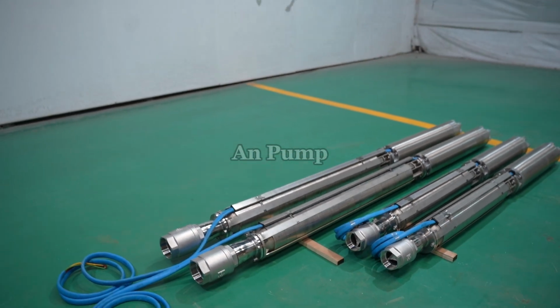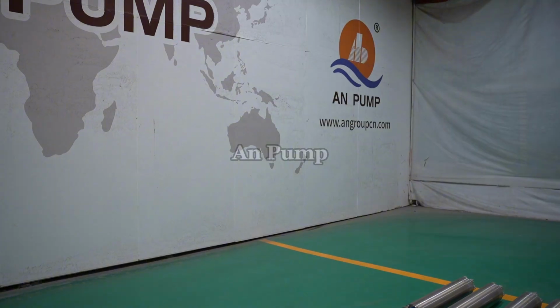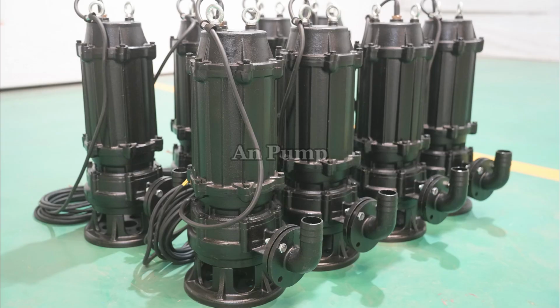Motor cooling is critical. In most designs, the surrounding fluid cools the motor. For clean water borehole pumps, that works directly. For sewage and slurry pumps handling warm or low conductivity fluids, an internal oil-filled or water jacket cooling system may be used. Shaft sealing is paramount because motor flooding is a catastrophic failure. Modern submersible pumps typically have two seals, a primary mechanical seal on the pump side, and a secondary seal on the motor side, with a barrier chamber between them. A moisture probe can alert operators before the motor fails.